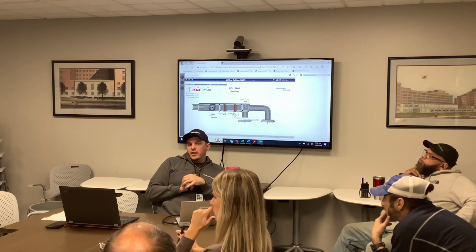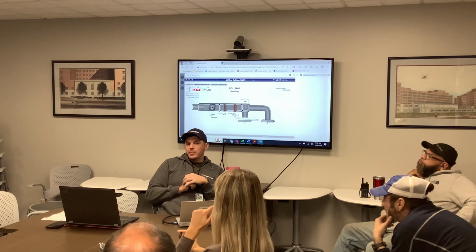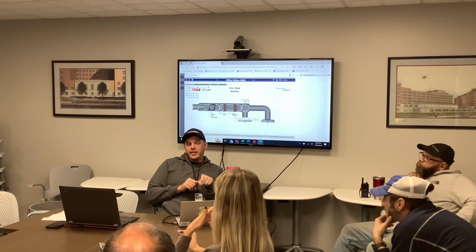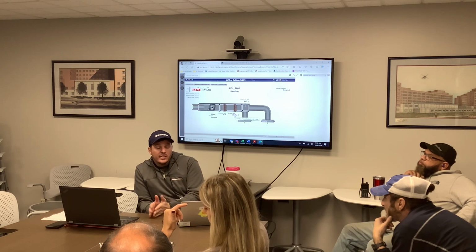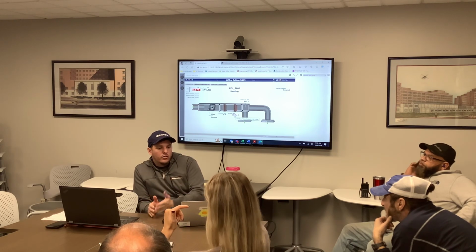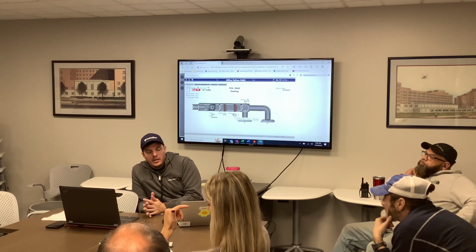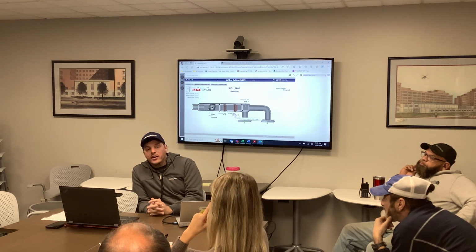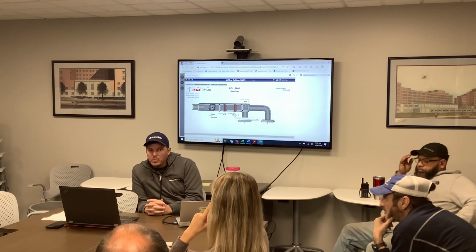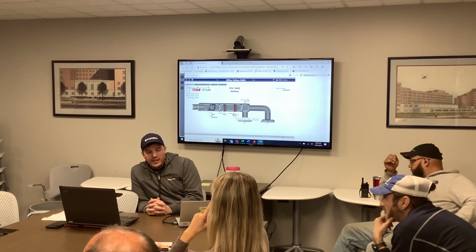Yeah, so this is a great question for the engineer, and that's why an RFI was put out. Because what I'm gonna have to do to solve this, if there's chilled water in this system, I'm gonna have to disable the heating on it, right? So it can't do this. And if it does that, how you currently have the steam valves wired in, they're not gonna open those steam valves as well, because the heat is gonna be disabled. So you won't have any heat.